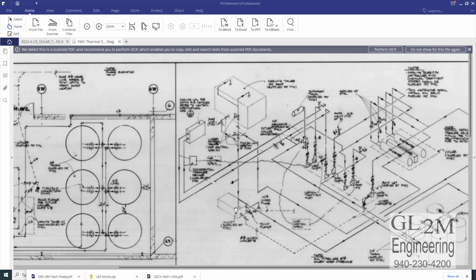So it has an indoor sump down below, because otherwise you have to put a heater in this sump, and that's expensive, it's wasteful. This is the pump skid. It's got 4 Bell and Gossett pumps on it. These devices here are suction diffusers that clean up the water entering the pump. It allows me to basically build a smaller area for the pumps.